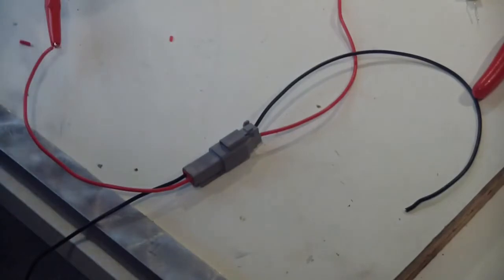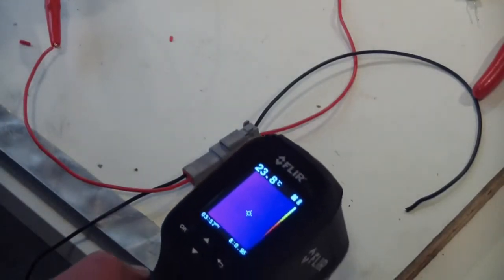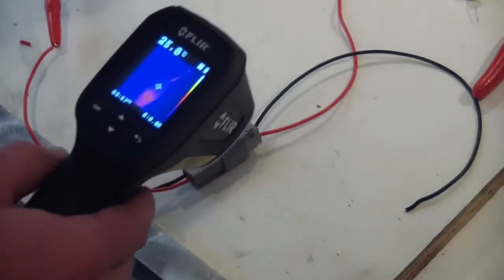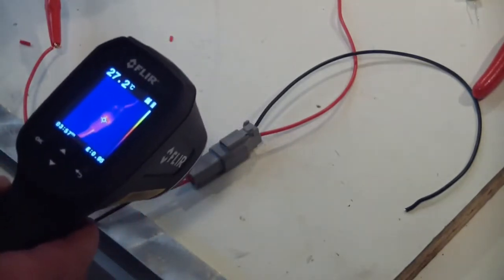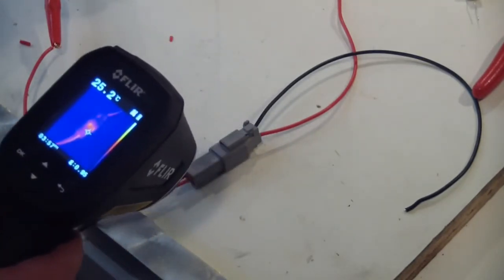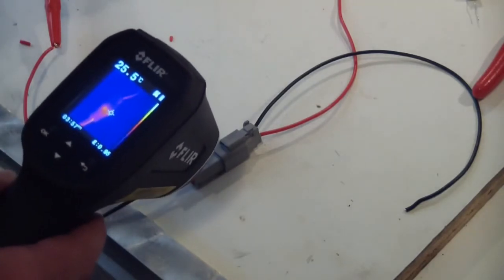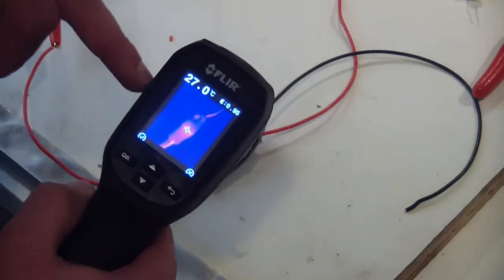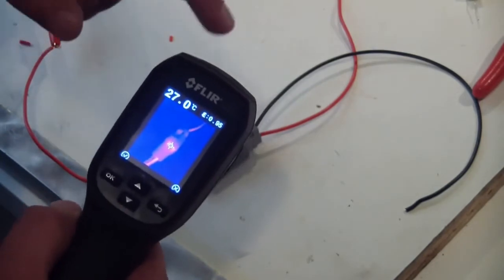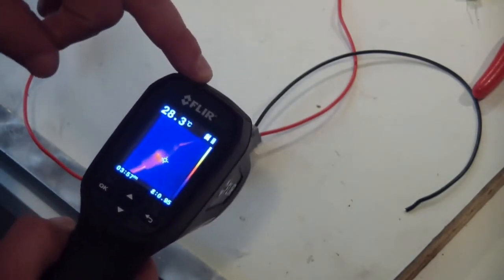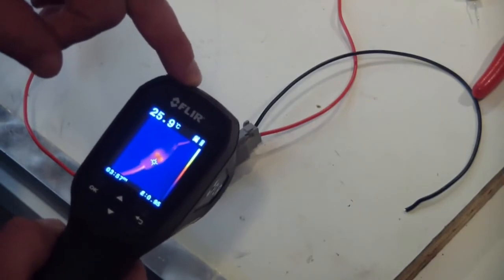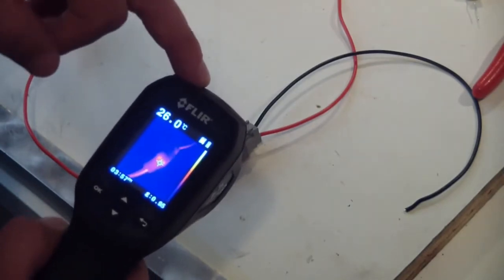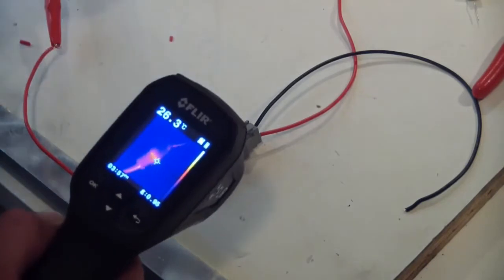Okay. So we got this powered up now, just under a moderate low 0.5 amps and you can see here, she's hotter than a $2 pistol. Clearly something wrong with that connector. We didn't even have to put our meter on it. And the interesting thing is you can also take a snapshot. It saves it to an SD card. You can put it in your YouTube video or show your customer or she who must be obeyed in order to justify the $500 purchase.